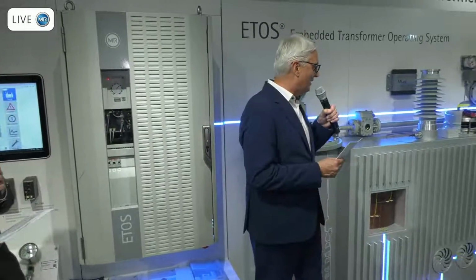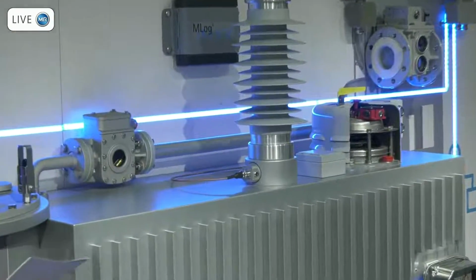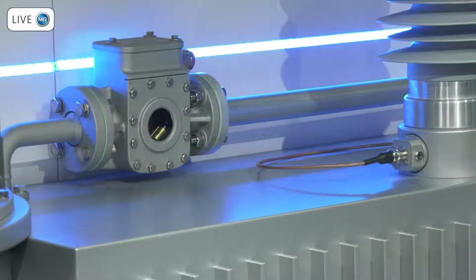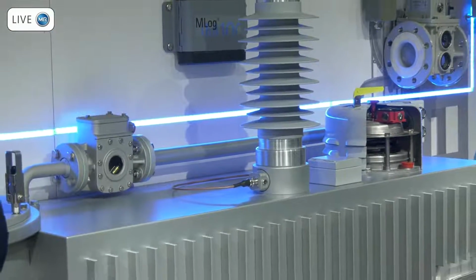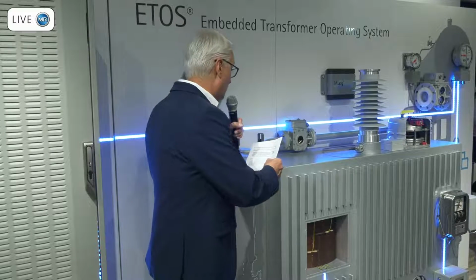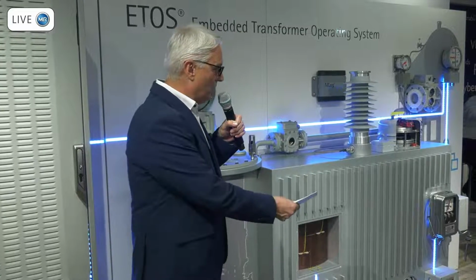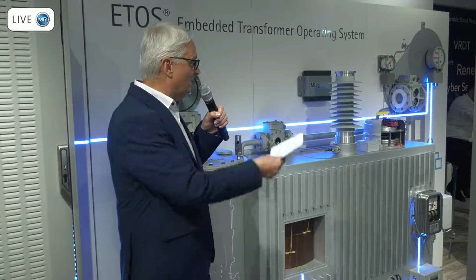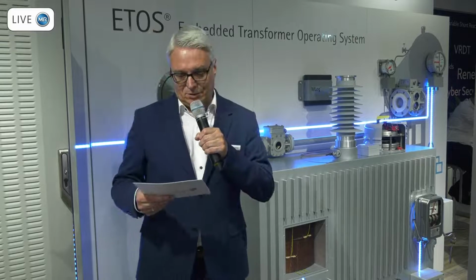If you look to my left, you see some of the parts or features of the ETOS we can have. Next to me, there is a small sensor called the Vibro Acoustic sensor, which means vibroacoustic monitoring. It records any noise done inside the tap changer. It's a self-learning system, and it takes care that if the sound has some irregularities, the sensor detects that. Other features are, for example, bushing monitoring. We have a DGA sensor over there. We have the classical instruments like oil level indicator, temperature measurement. All of these things can be connected to our ETOS.